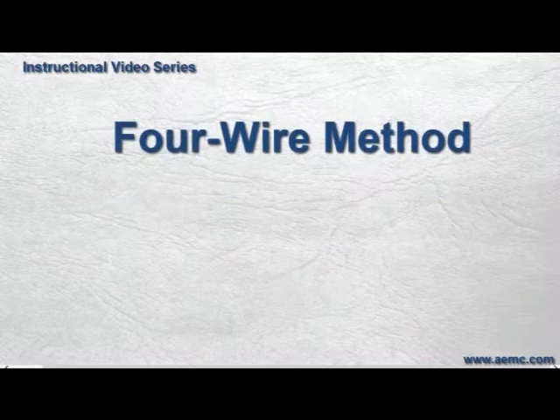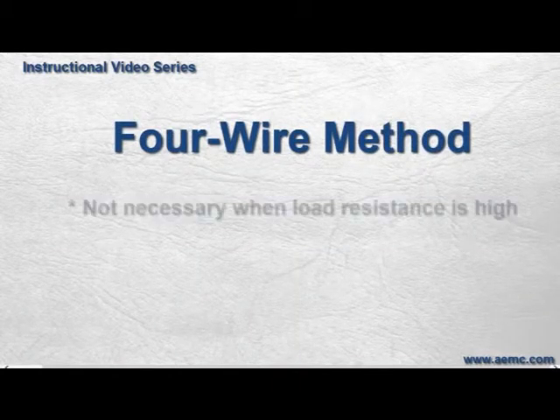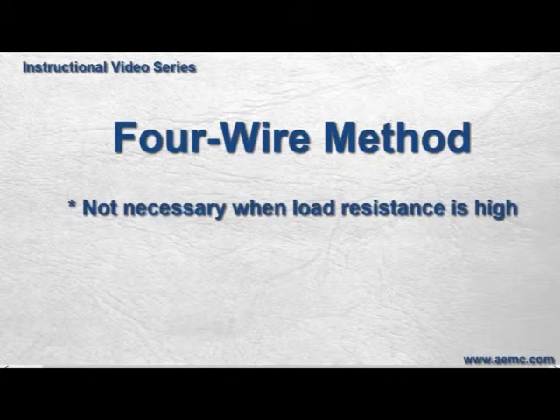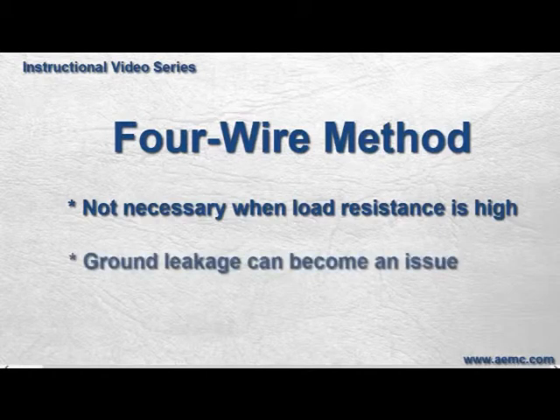Note that the four-wire method is not suitable for all applications. For example, when the load resistance is high, the resistance in the probes is relatively smaller as a percentage of the overall resistance, and therefore does not introduce an unacceptable margin of error. Further, measuring high resistance loads requires that the constant current be kept at very low levels.